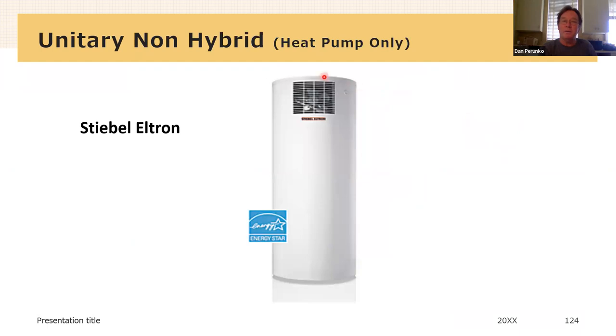In this scenario, there's no electric resistance coil. So this is sort of the highest efficiency unitary unit, meaning all one piece, available because it has no electric resistance coil. And these have been installed with families of 4 and 5 people and kept up just fine. If you do things like wash the dishes and leave the tap running the whole time you wash the dishes, you can deplete this machine, right? Like its recovery periods are very long. So you have to be a little careful about water usage, but really actually very successful machine.